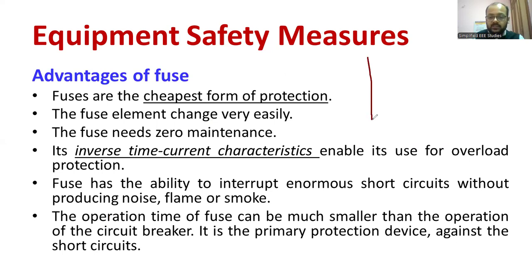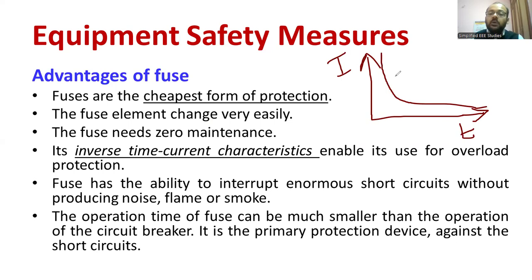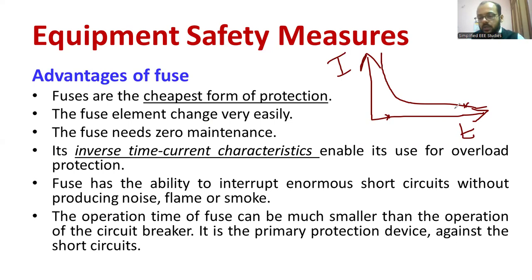What is meant by inverse time-current characteristics? If you plot current versus time, you get a hyperbolic graph. For a high magnitude of current, the fuse will act very fast. That is what is called the inverse characteristic of current and time. For a lower fault level, it will take a little more time to act — no problem. This is called inverse time-current characteristics. These are the important advantages of the fuse.